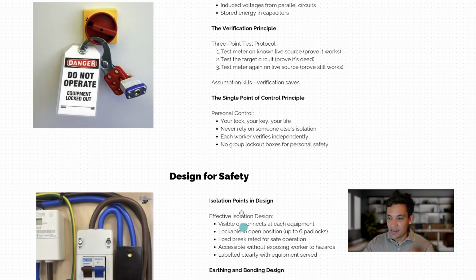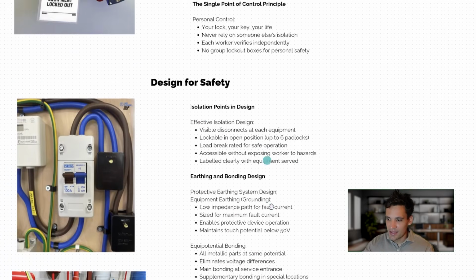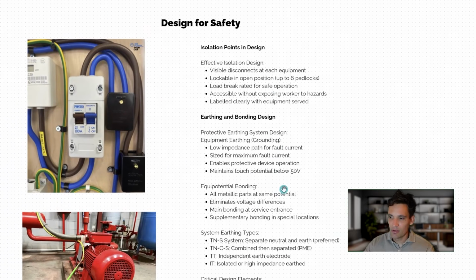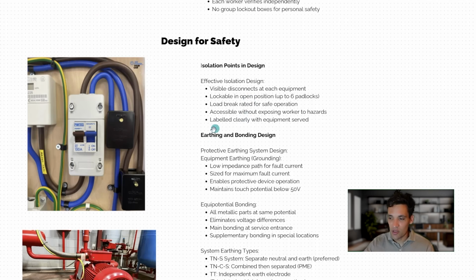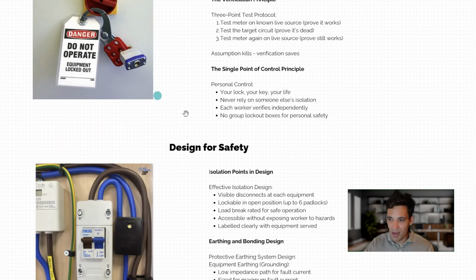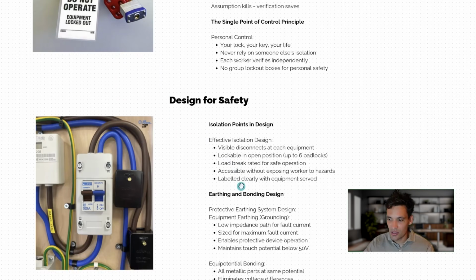Electrical safety starts in the design phase. It's not just the construction problem. It starts all the way back when we're looking at the requirements of the project and trying to understand them. And that is why electrical designers are inherently part of the safety process. Simplest way this is implemented is with isolation points in the design. Every component of an electrical system should have visible disconnects at each equipment, should be lockable in the open position. So you should be able to place a padlock to isolate the circuit.